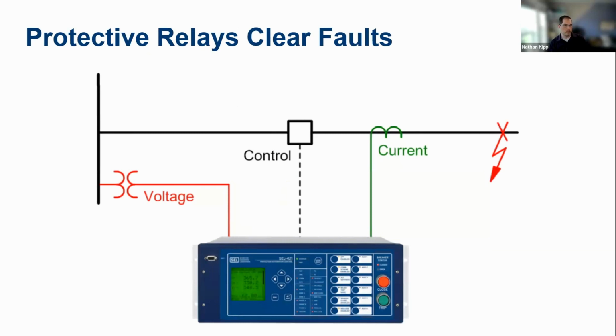What we're doing with our relays is we're looking at voltages and we're looking at currents on the line, detecting when things go out of bounds. So if current spikes above a preset threshold or voltage drops below a preset threshold, then we'll take an action such as trip a circuit breaker. And we don't have the circuit breaker built into us. We're more like the HVAC example where we're the thermostat, right? And we're recognizing what's happening on the electric system and triggering something else to take the output action, right? In this case, it's a circuit breaker.